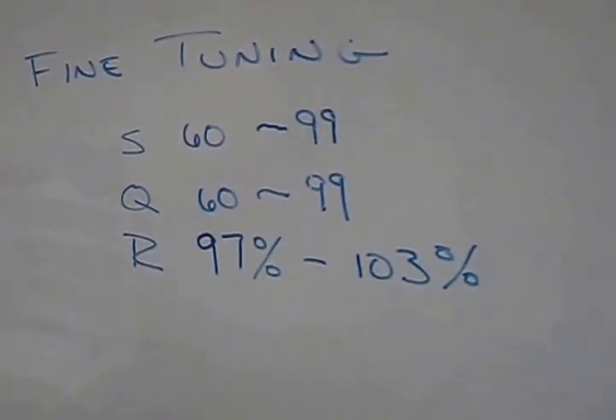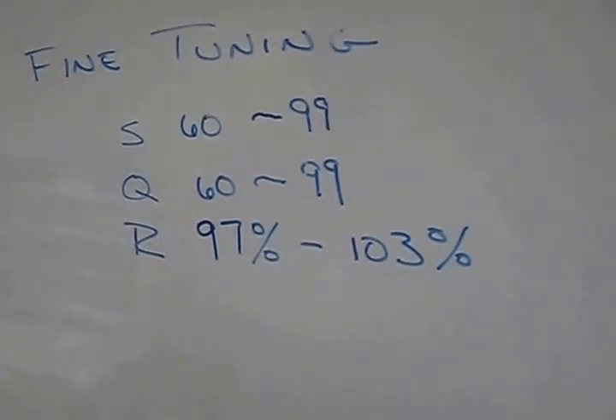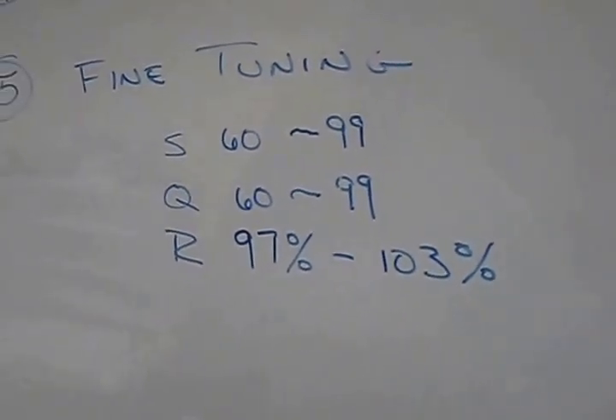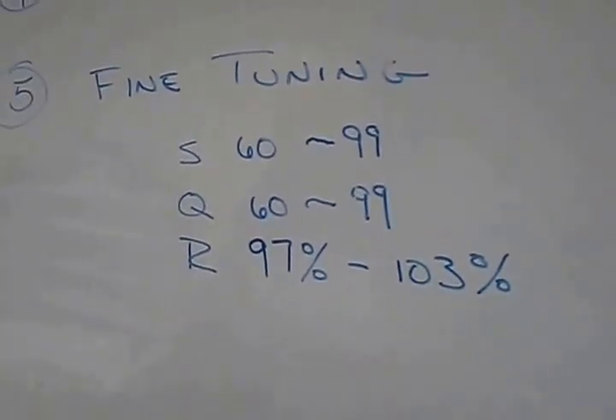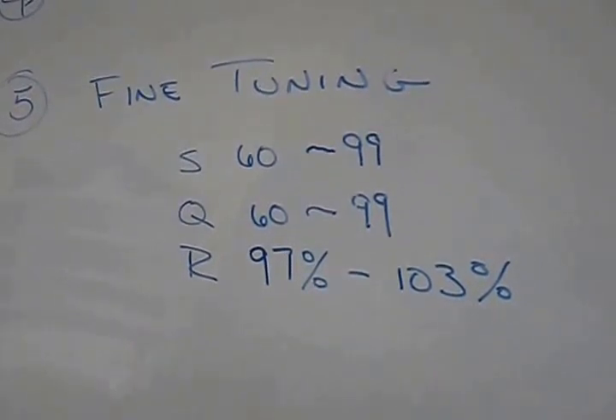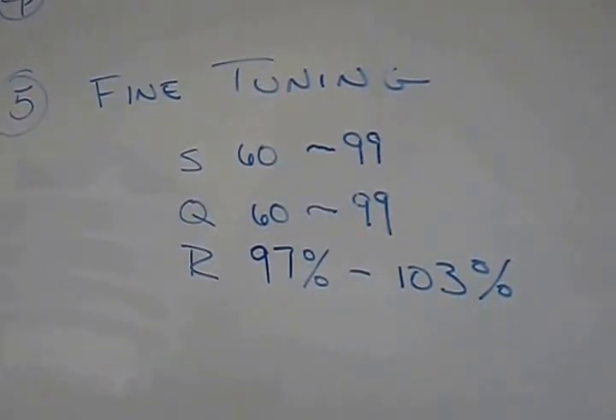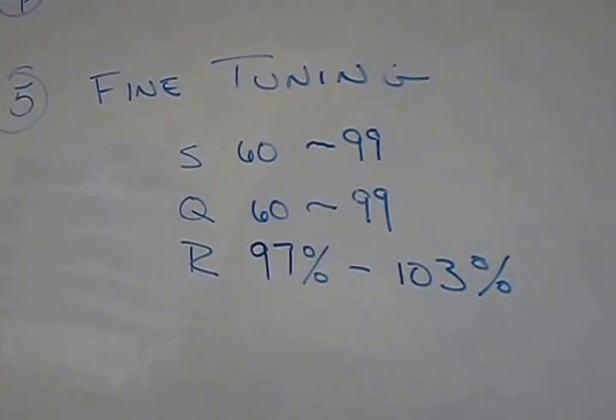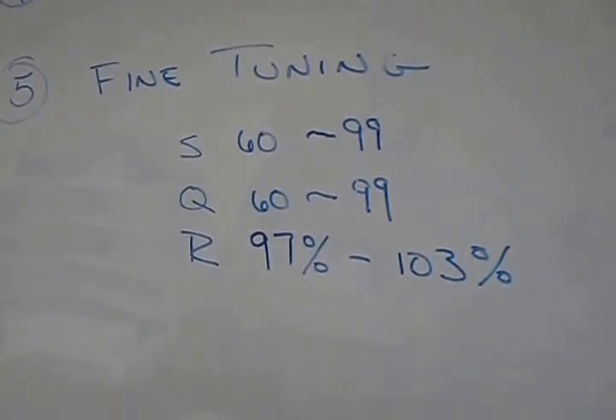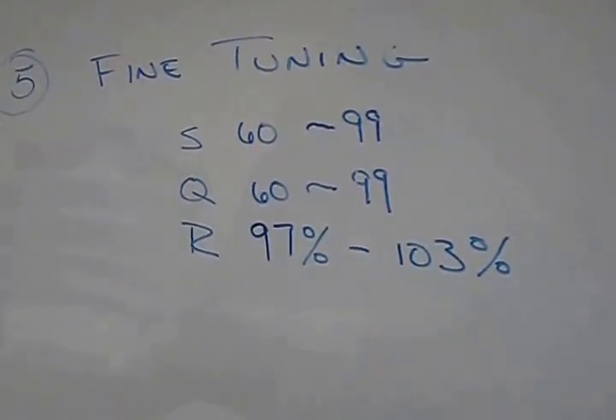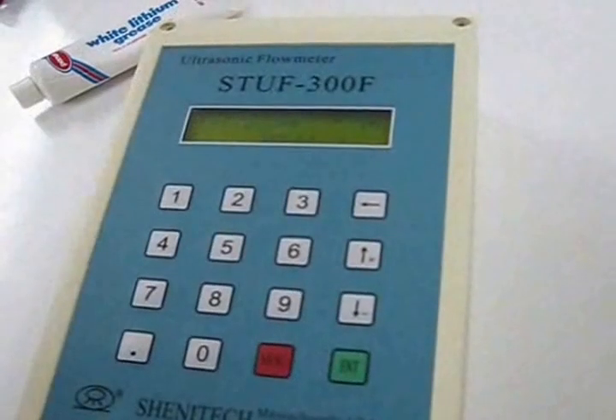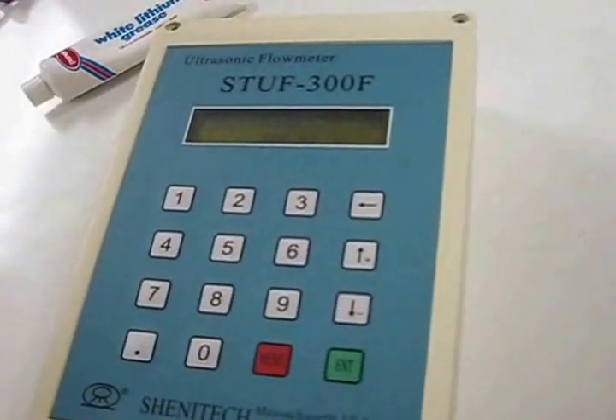If your flow meter is not within these parameters, you may have to go back and re-enter the parameters in menus 11 through menu 24, making sure they are correct. You also may need to adjust your transducers, making them a little closer or a little further away from each other. After your flow meter is fine-tuned, your installation is done.